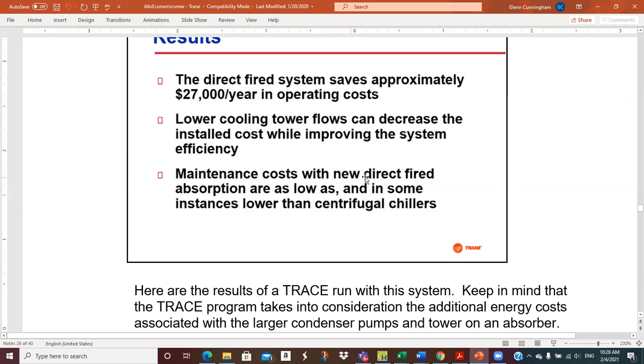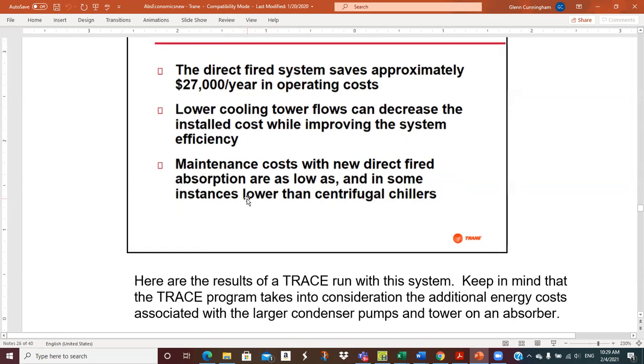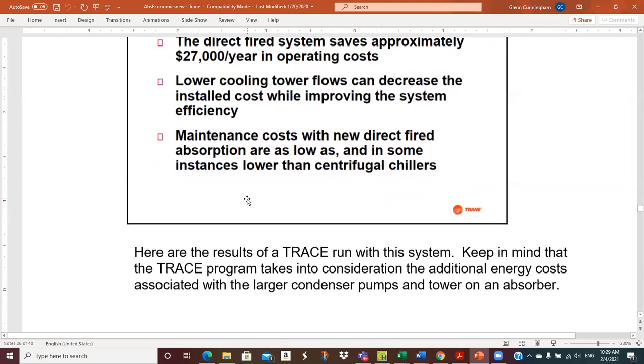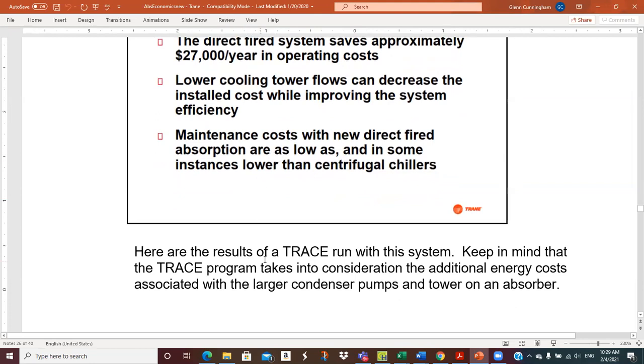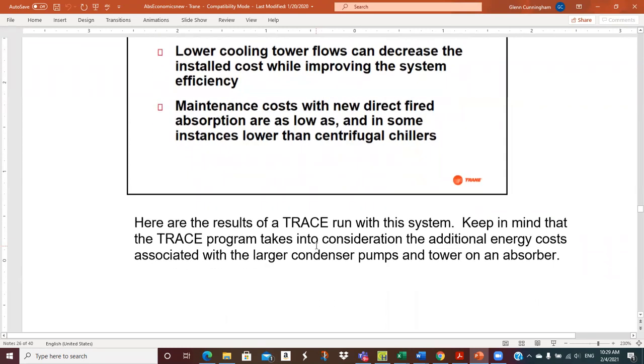Maintenance costs with new direct fired absorption are low, and in some cases lower than centrifugal. We'll have some slides here in a minute. That's one of the raps that absorption chillers have had over the years, that they require a lot of maintenance. They did this analysis in the Trane TRACE program, which is very similar to the Carrier hourly analysis program that you guys are operating for homework. So it does about the same thing.